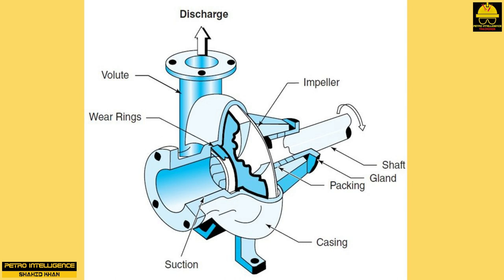The volute is a gradually widening cavity inside the casing of a pump. The inlet is sometimes referred to as the suction eye. Fluid comes into the center of the impeller and is spun toward the outside of the volute. The inlet line is designed to run, when primed, full of liquid. The outlet line receives the discharge from the pump volute. Because the discharge line is wider than the inlet volute, fluid velocity slows, creating pressure.